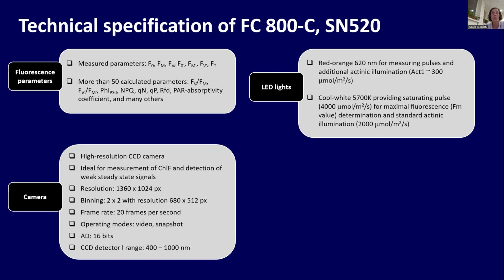This is a very typical combination of light, and we can get even more intensity from the LED panels. For example, from actinic 1 we can get more, but this is a setting that we have to provide to customers. Actinic 1 is for low light applications, where you need to tune low light intensities like 10 micromoles, 20 micromoles, for sensitive samples like algae, mosses. And the cool LED and actinic 2 is used more for plants. So this FluorCam is designed to be versatile for different organisms.